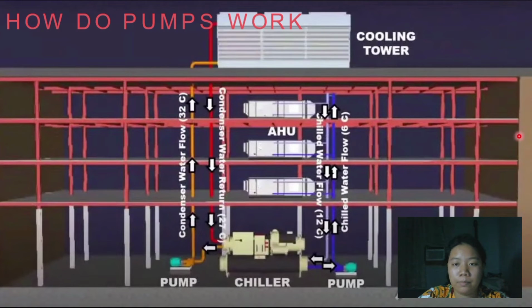A centrifugal pump moves water, known as condenser water, between the chiller in the basement and the cooling tower up on the roof. The chiller adds heat to the condenser water, and the cooling tower above cools it down by rejecting this heat into the atmosphere. The heat it rejects is all the unwanted heat from the building caused by the people, the sunlight, the lighting, and so on. It must also reject the heat generated by the compressor of the chiller.